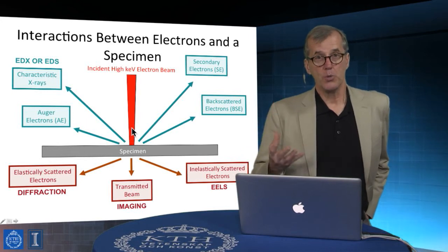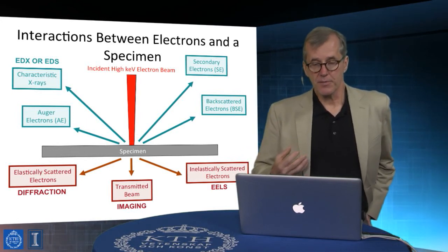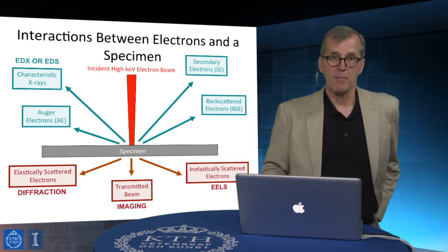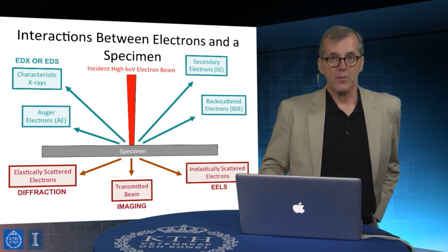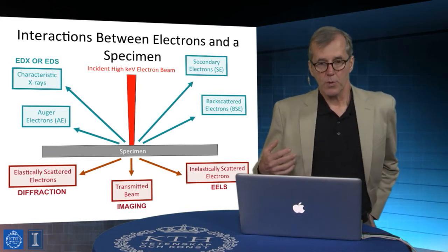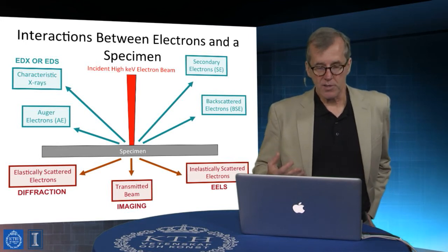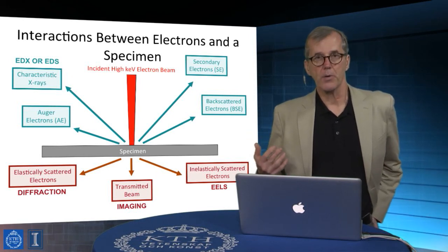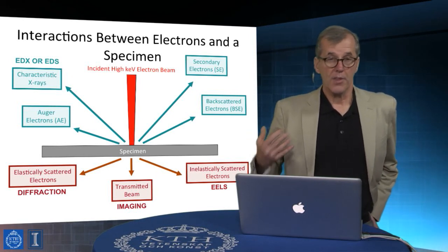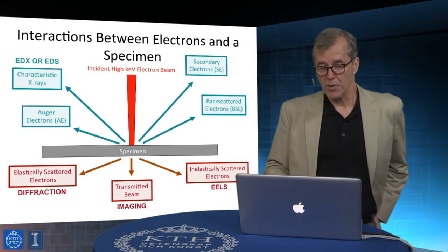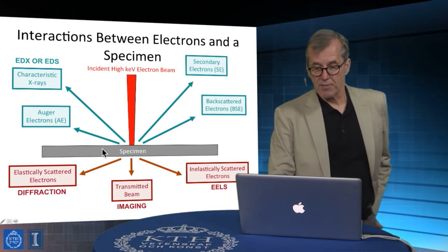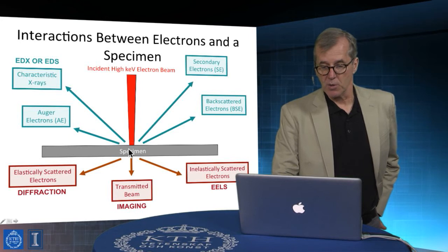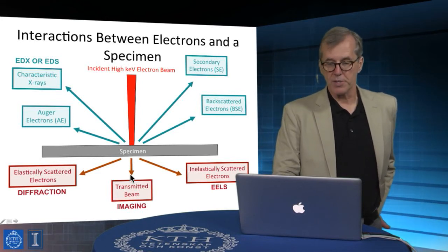We might choose different values of these accelerating voltages from the perspective of mitigating the consequences of beam damage. There would be a difference, for example, with regard to a microscope operating at 90,000 electron volts or 300,000 electron volts. But obviously, very high accelerating voltages would make it possible to look at thicker samples than would be possible with lower voltages. The specimens must be very thin because most of the interest is in looking at the electrons that actually come through the sample.